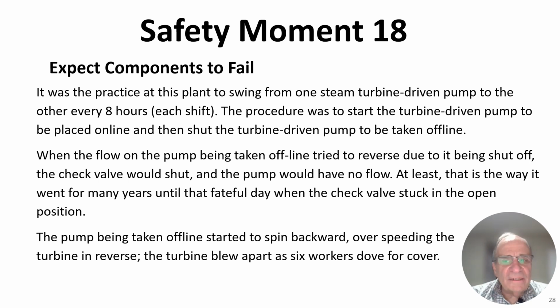Safety moment number 18. Expect components to fail. In one plant, it was the practice to swing from one steam turbine driven pump to the other steam turbine-driven pump every shift. So every 8 hours, one pump was shut down, the other pump was started up. And they would switch every shift from one turbine to the other turbine. The procedure was to start the pump that was not online, and then to shut down the other pump so that the pump that was just put online would take the load.